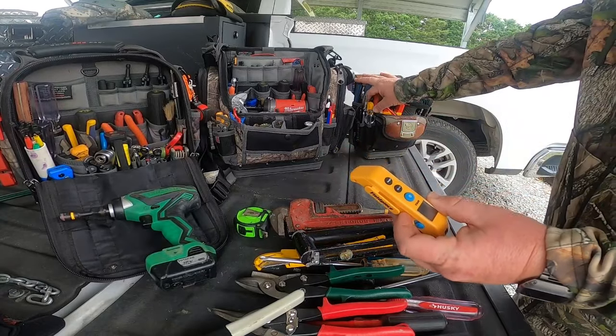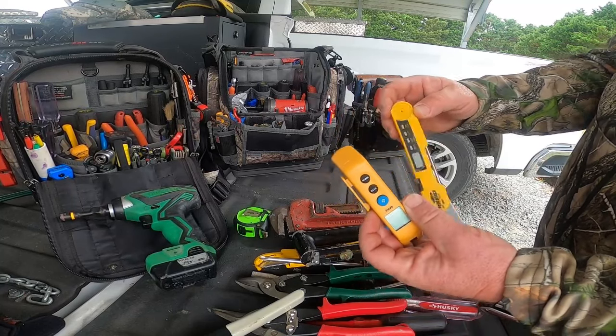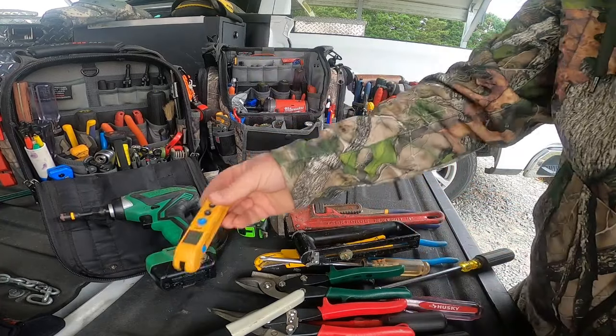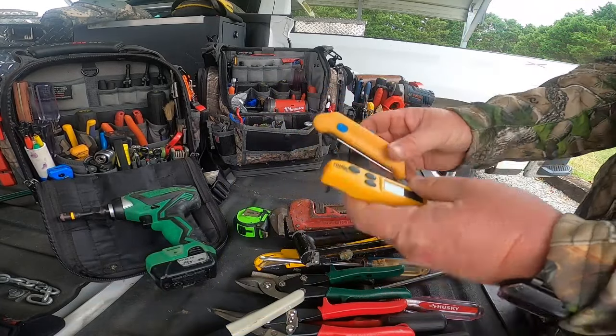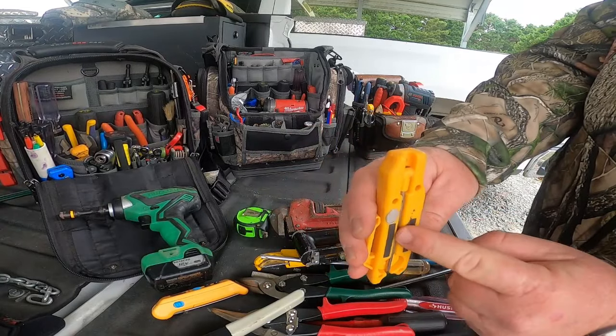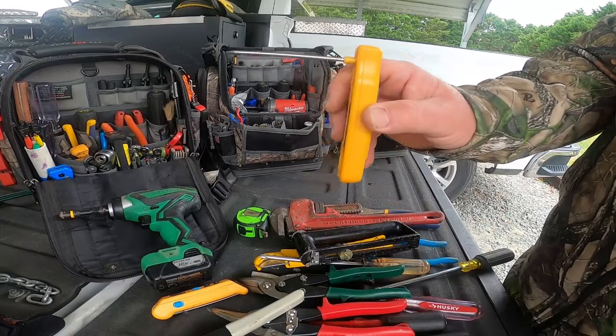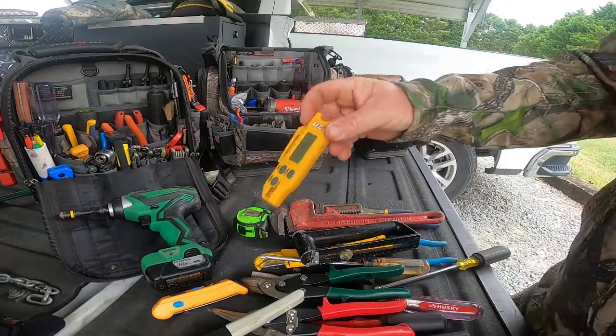Temperature probes - Fieldpiece makes two different types. You use them to check return temperature, supply temperatures, and check your temperature split. I'm partial to the UEI because it's shorter and more compact. I like this one especially because it has magnetic strips on the back so I can stick it in a plenum, push it to the wall, and the magnet holds it. I can turn it however I want to read it. A good temperature probe is essential.